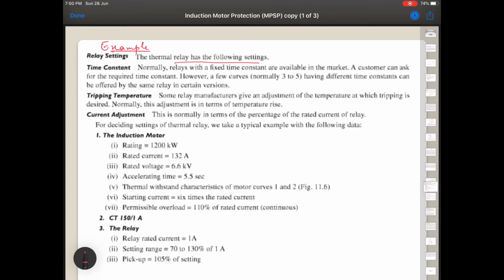Then temperature: some relay manufacturers give an adjustment of temperature because the same relay will be operating in different environment conditions. So adjustment in terms of temperature rise is normally given. And current adjustment is normally in terms of percentage of rated current of the relay. So we'll try to see what current setting has to be done for the induction motor given with the following data.